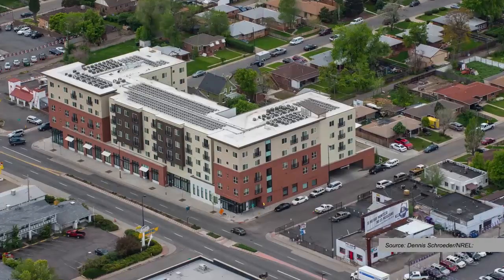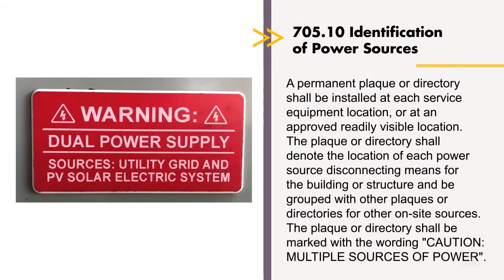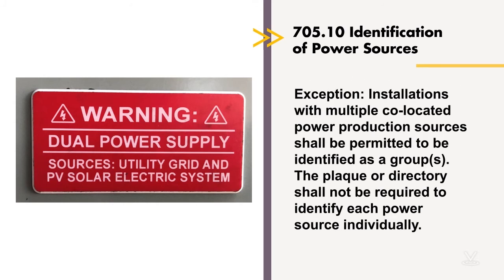705 covers everything else. If you have multiple power systems on a building and they're not connected at the same location, you've got to follow the rules of 705.10. This says that we have to have a plaque at each one of the connection points that says 'Caution, multiple sources of power.' The service is going to have this placard on it, showing where all these other sources are connected. However, if everything is co-located at the same place, coming into the same location, we're not required to have a separate plaque. And that's what this exception is talking about.